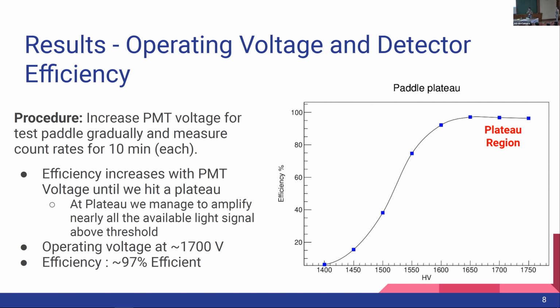What we do is we gradually increase the PMT voltage with a gap of 50 volts, and then we collect the data for 10 minutes. Then we try to find out all the counts we are getting from the coincidence units, with and without coincidence units, separately. We divide the 4-fold coincidence by the 3-fold coincidence to get the efficiency.